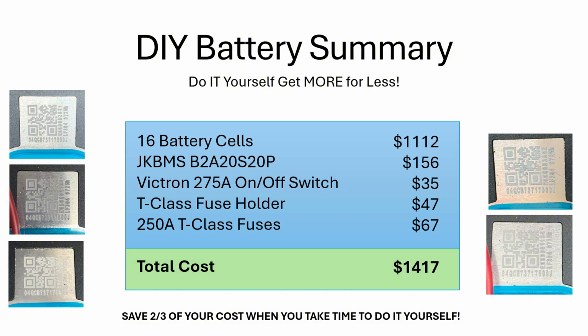We had 16 battery cells at $1,112, a JK BMS, the B2A20S20P, which is basically a 2 amp balancer, 20 cells and 200 amps of power for $156. The Victron 275 amp on-off switch for $35. The T-Class fuse holder for $47, and a 250 amp T-class fuse. I did buy two, one for a backup and one for the real one, for a grand total of $1,417.